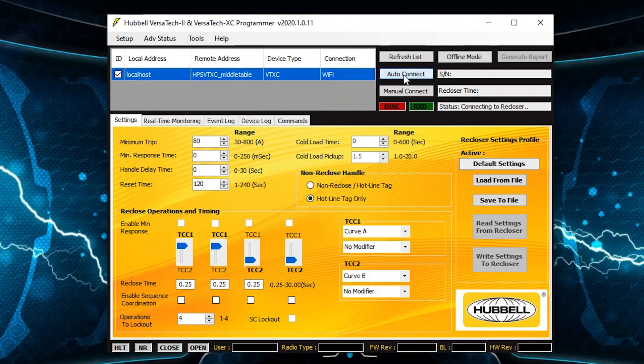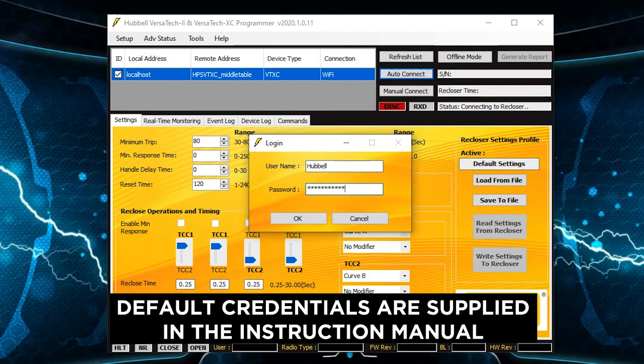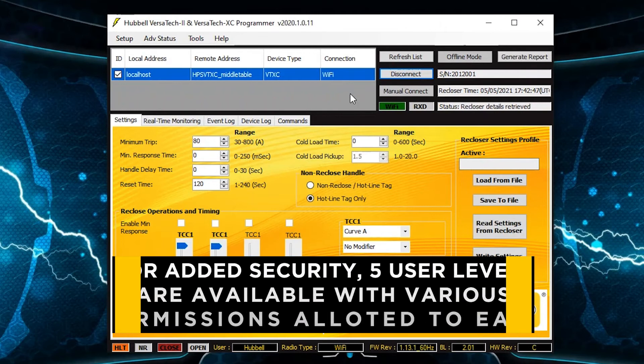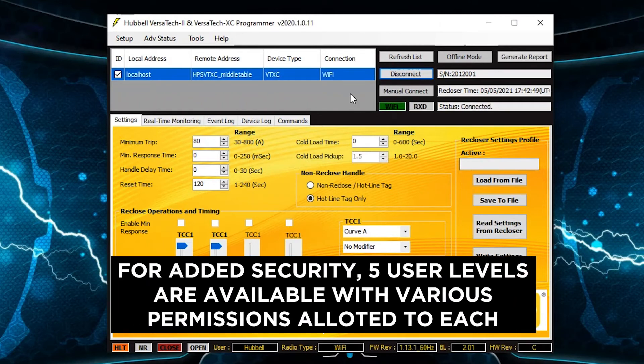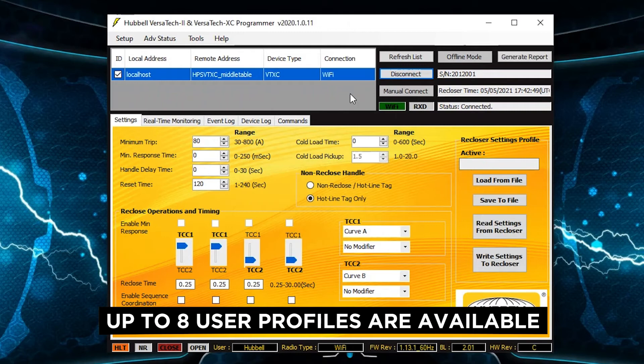A main difference the user will see when connecting to a VersaTech-II or VersaTech-XC recloser is that the UI requires the user to enter a username and password associated with a user profile. Default credentials are supplied in the instruction manual for an administrator profile and may be changed by the user at any time. For added security, five user levels are available with various permissions allotted to each. Each user profile may be assigned a user level when created, and up to eight user profiles are available for programming.